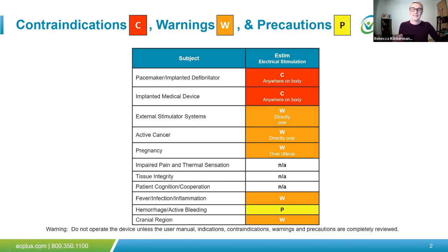And even if the device is not used, I get this question fairly often. So a patient may have a deep brain stimulator or cochlear implant in place, but it's not used, or maybe a portion of the device was actually removed. Often those lead wires are left implanted. So even if the implant's removed or it's not being used, the presence of those lead wires would remain a contraindication. Electrical stimulation on patients with implanted metallic or electronic devices should not be used, and it may cause electric shock, burns, electrical interference, or death.